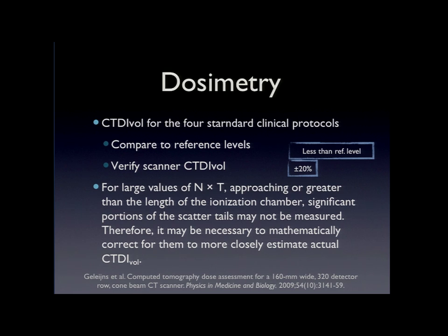Your scanning conditions can really affect what's going to display. If you change the field of view, that can change the phantom that's used as a reference. So that's the thing you have to be careful about. When you're recording your data, be sure the physicist has recorded which phantom is the reference for the dose that he determined for all those different protocols.